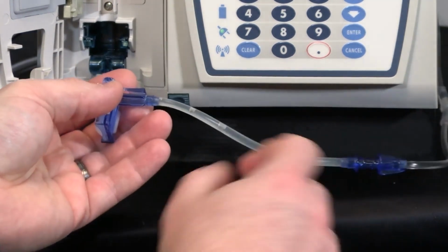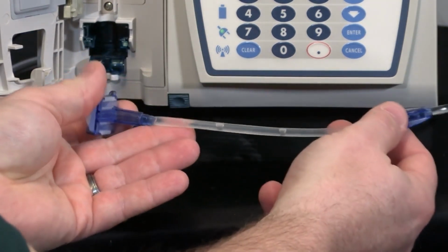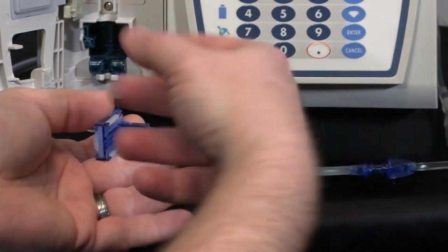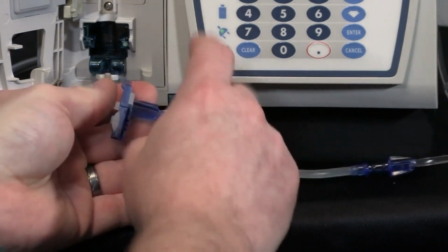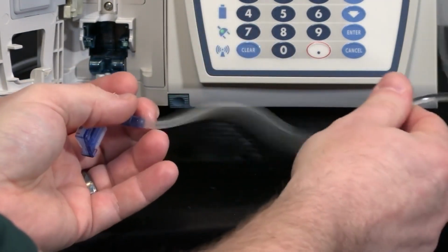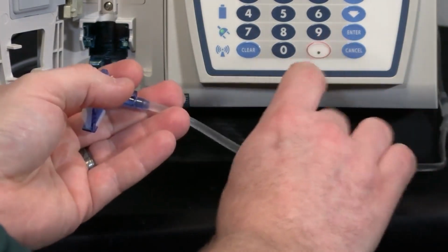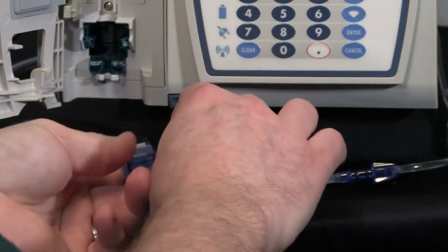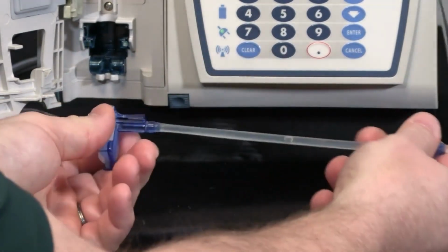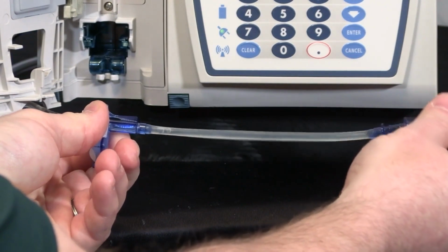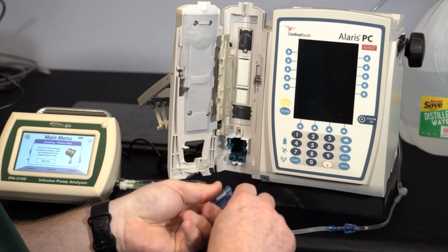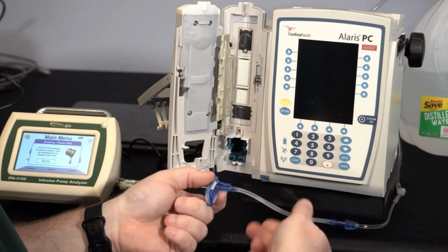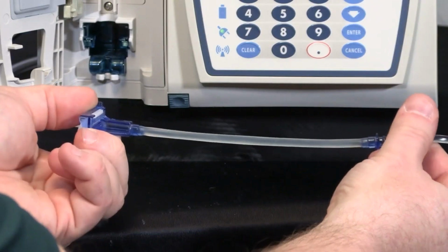And now here we can see that some bubbles are stuck in the tubing, right? If I were to run a flow test with that, the bubbles may come through and cancel my test. So all I have to do is flick the tubing a little bit while we're in this drain mode, and it's actually going to pull fresh fluid all the way through. And now we've got a bubble stuck down here. We just get that to flow through the unit. There's another one. And once we get all of these out of the tubing, I want to make sure we knock these loose. Now they're past the bubble detection sensor, and we should be ready for testing.